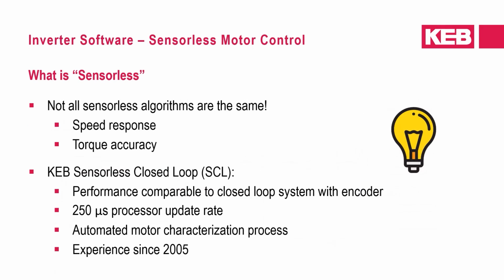It should be noted, though, that not all manufacturers' sensorless algorithms are equal. Although a comparison may be difficult to quantify, the key characteristics include the speed control response and the torque control accuracy. In this regard, KEB sensorless closed-loop software is very high performance and comparable to closed-loop systems with an encoder. This is possible due to the very fast processor update rates, accuracy of the motor model, which can be characterized with an easy-to-use motor characterization learn process, and KEB's experience with sensorless know-how dating back to 2005.